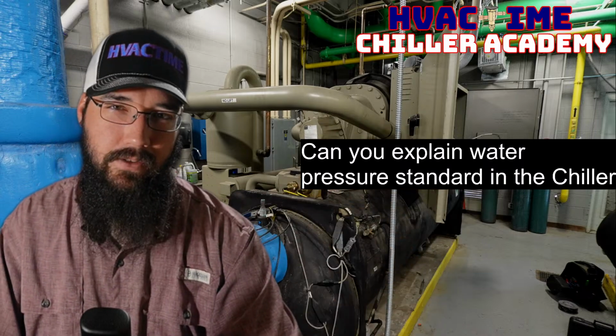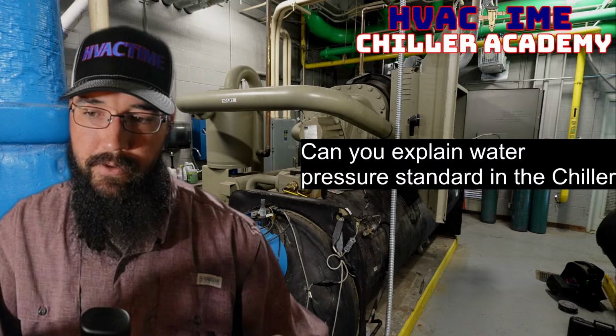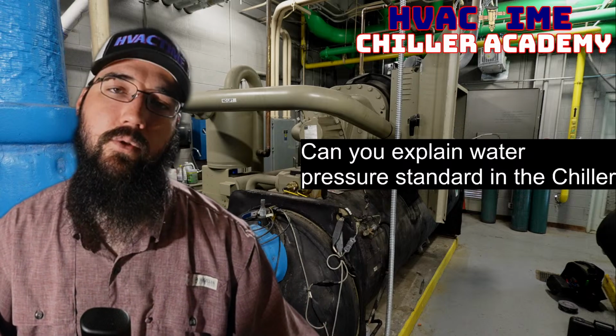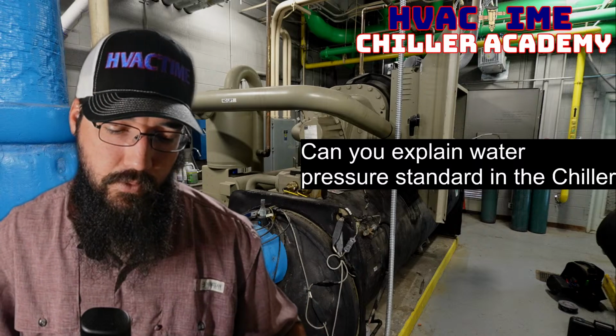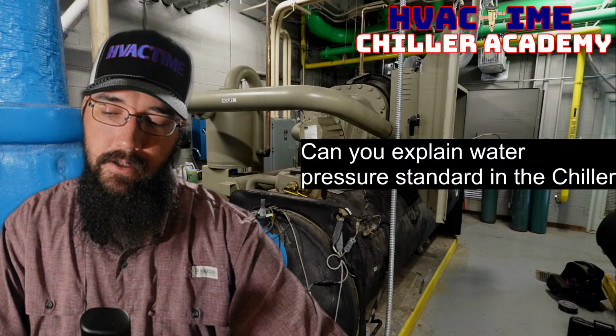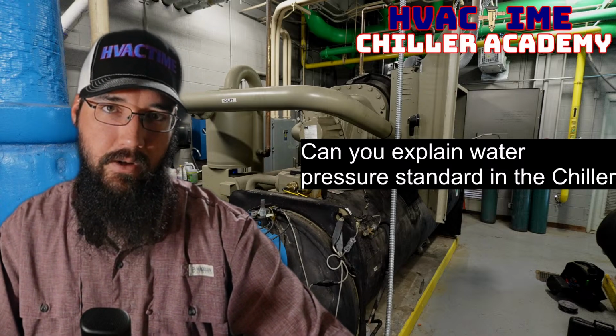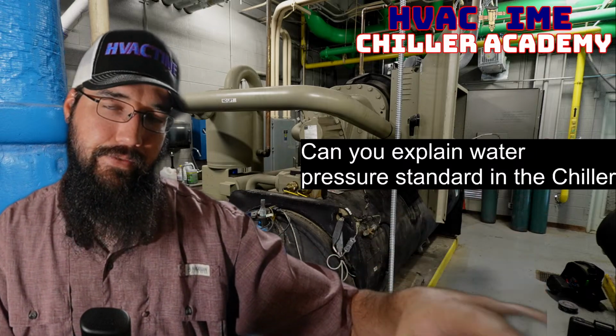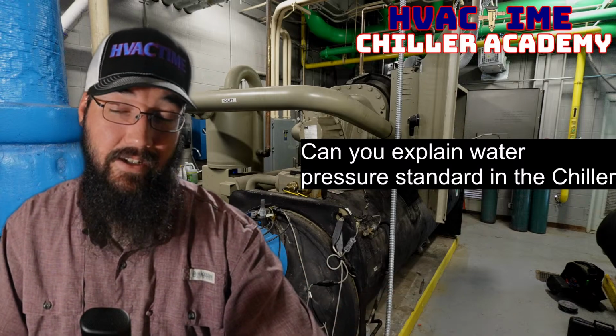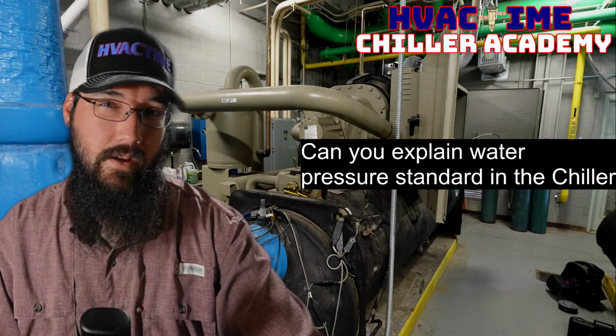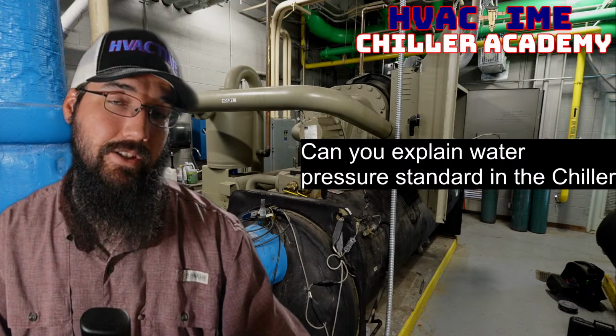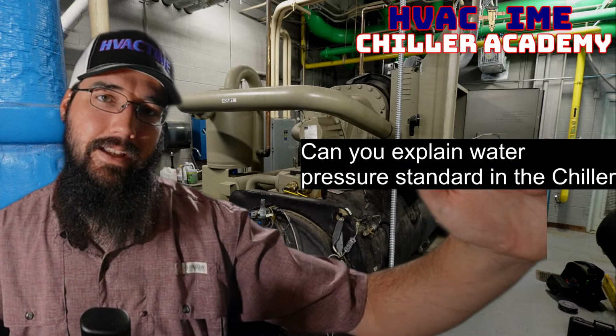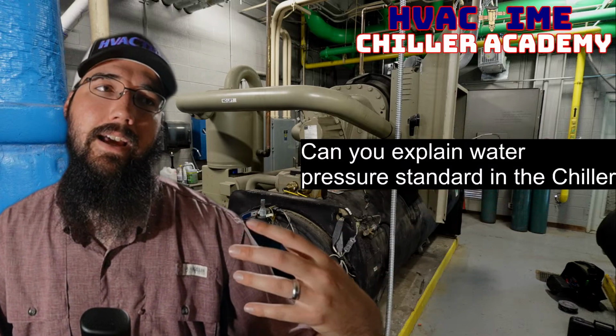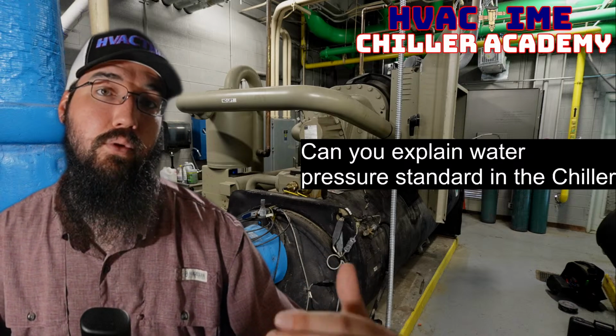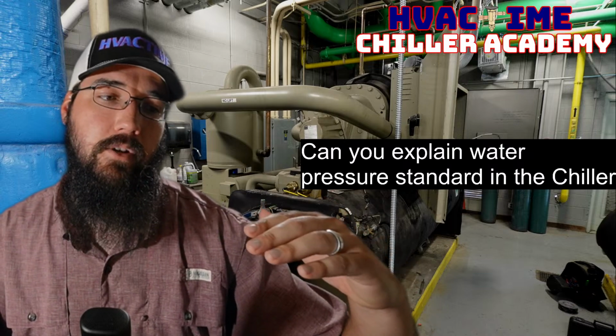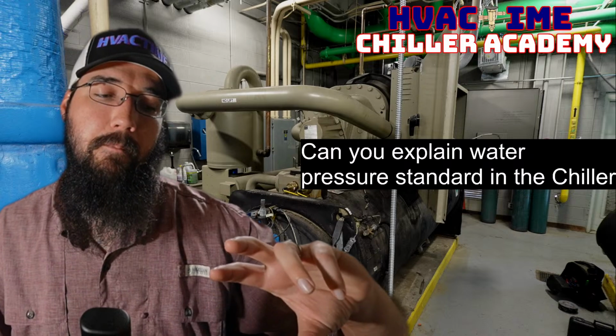So even though at the pump itself, and I go over this in much better detail and structure in the introduction or in the certification course, so if you are enrolled in that, I would suggest go back and review that a little bit. But just ad hoc here, even though you may have higher pressure at the pump, because the actual loop volume is insufficient, you can still create a cavitation issue, even though technically you've got 50 psi coming into the pump. And that's strictly just because of elevation. It's not because there's actually adequate water volume. So what I like to do is, once I get that elevation psi that I know that I need, I personally like to add 8 to 10 psi of pressure over that on my return or my suction pipe coming back to the pump, above that zero.